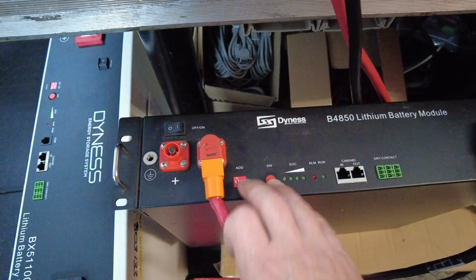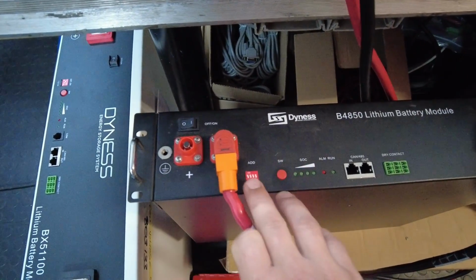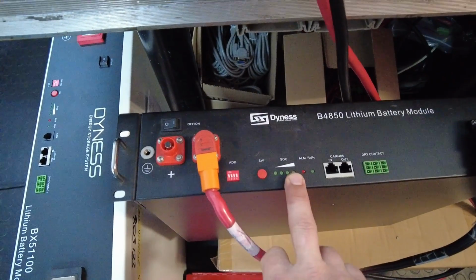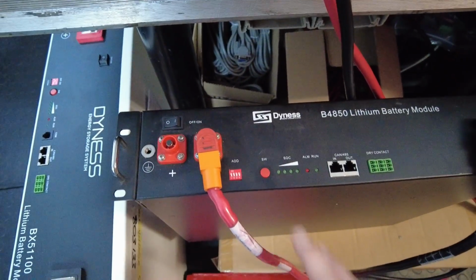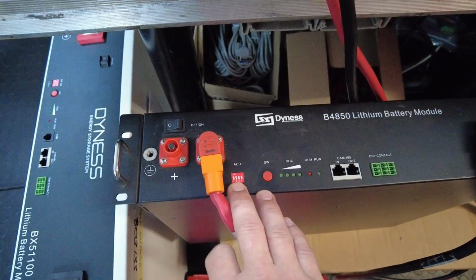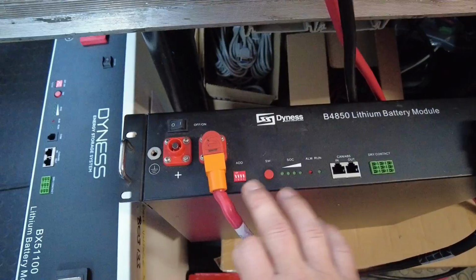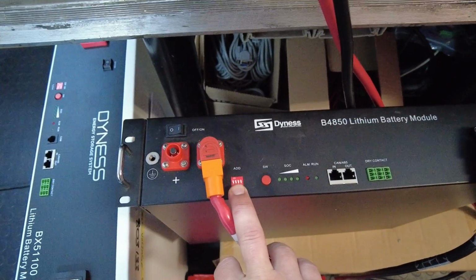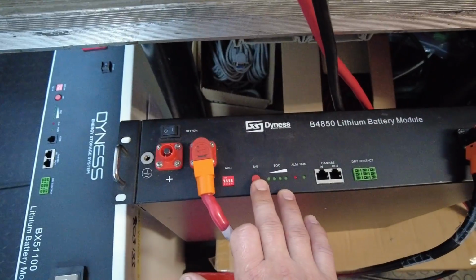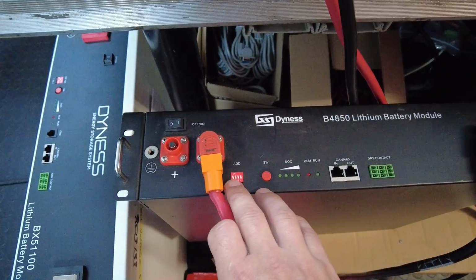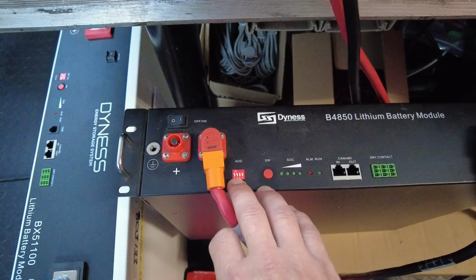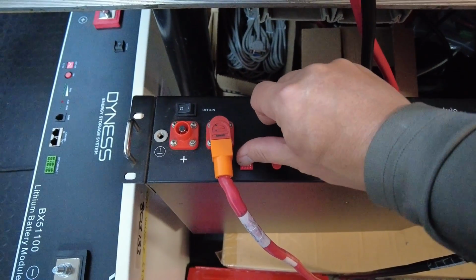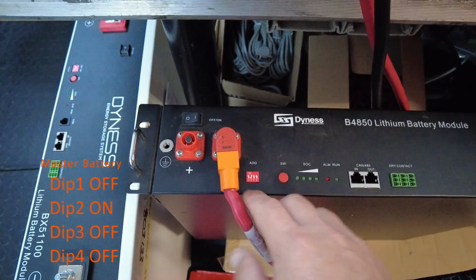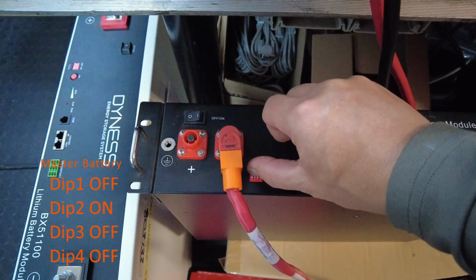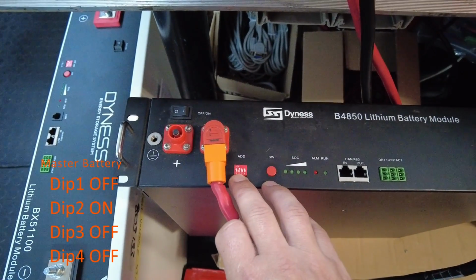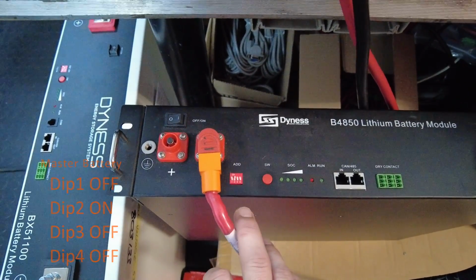For the dip setting on the battery, note the setting needs to be done while the battery is in off state. If you make any changes to this dip setting while the battery is on, then the changes will not have any effect whatsoever. So make sure it is in the off position. Currently it is off. Looking at the dip switch block, dip number 2 you need to put in the on position. So dip number 1 is off, dip number 2 is on, dip number 3 and 4 are off.